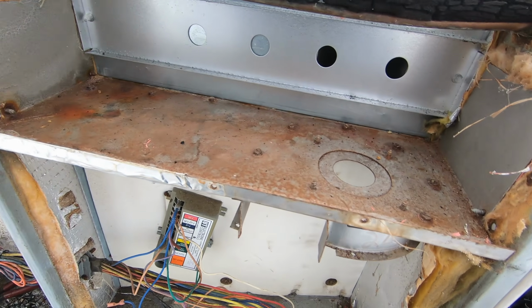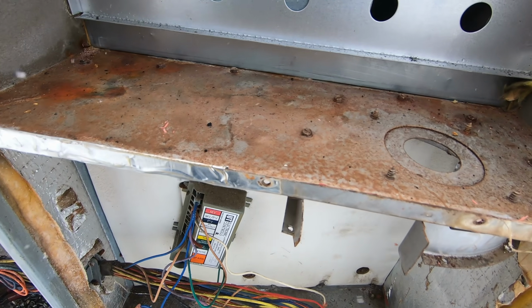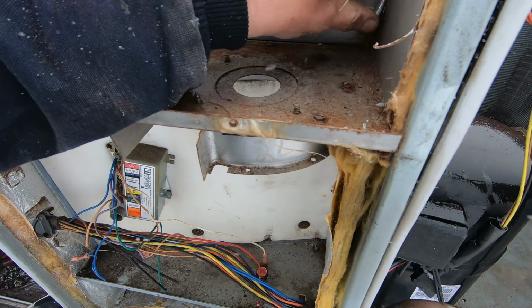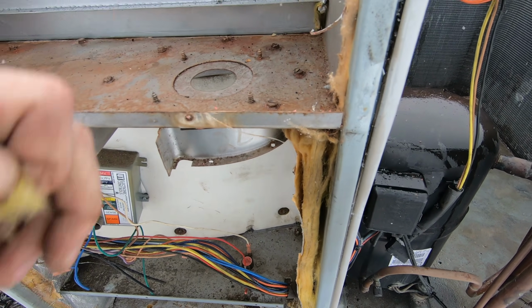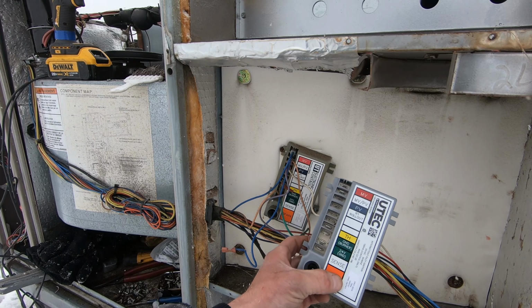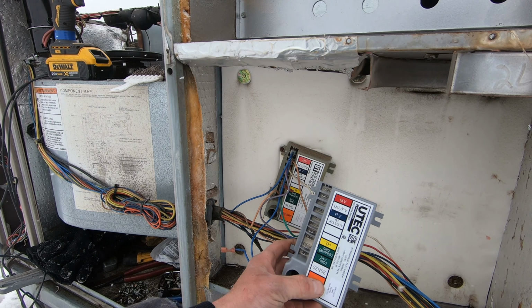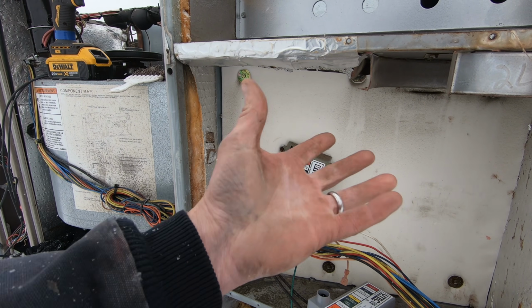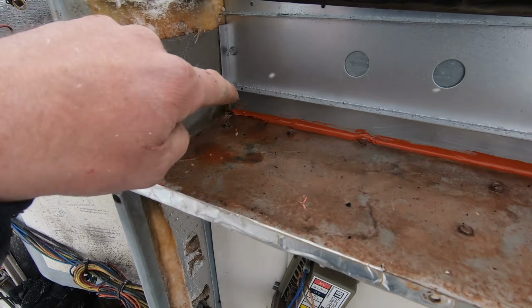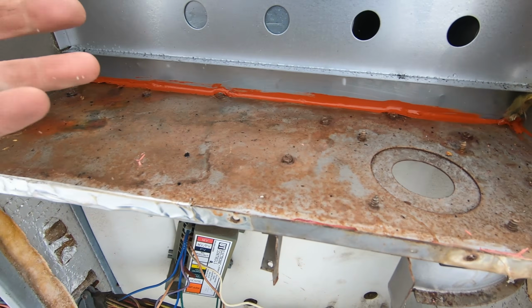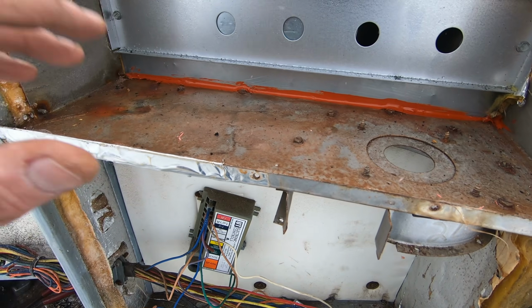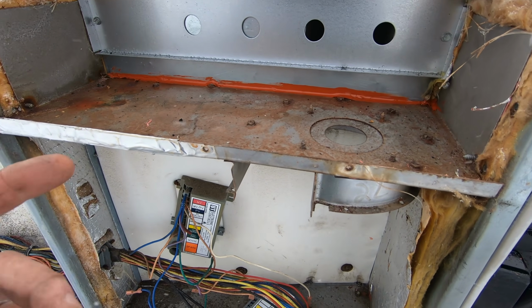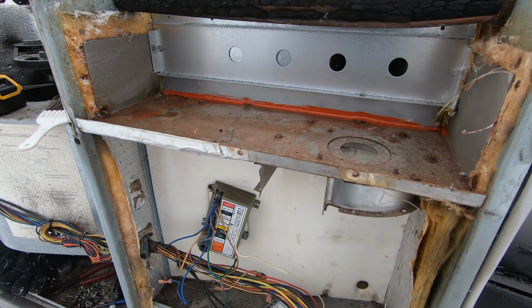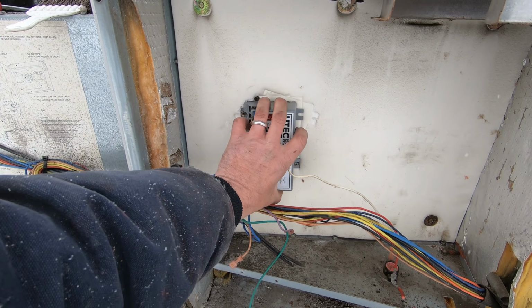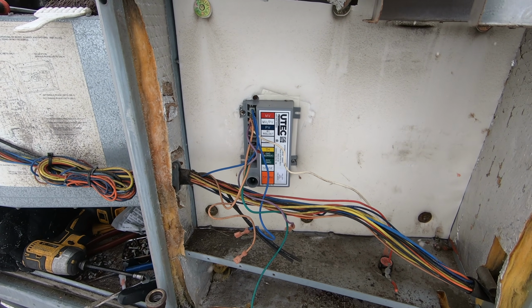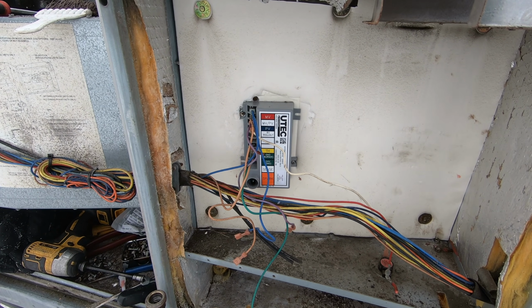Next thing I'm gonna do before I put this collector box back in place is I'm gonna run a bead of high temp silicone in here just to seal it up as good as we can. I got a new ignition control here. I'm gonna go ahead and mount that and get that replaced, and then we'll be good. I've got my silicone in there as good as I can. It's soaking wet, so I've got it sealed up as good as we can. Once it fires, it should cure pretty quick. I got a new screw in here, that way it's mounted nice, looks good, and I got it swapped out.